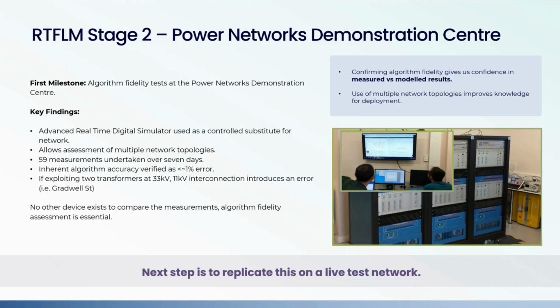So I think what John was going to continue to say there is that the flexibility of the real-time digital simulator as a control substitute for the network allows us to quite easily assess multiple network topologies and multiple scenarios over quite a short space of time. So they completed 59 measurements over the course of 7 days. And it really did add a lot of value in terms of the next stages of the project, in terms of how we would go about deploying these on the network, because we were able to test out more unusual types of configurations that would be difficult to test otherwise. But obviously, we also tested all the prescribed and intended ways of deploying the device, and the Power Networks Demonstration Center independently verified that the inherent algorithm fidelity, algorithm accuracy from these tests has to be within 1% error.